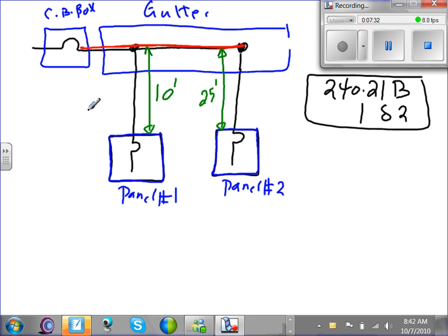All right. If you look at that, this is just a quick review of the 10-foot taps. Here's what the 10-foot tap tells you. Rule number 1, you can't go further than 10 feet. Duh, Chad, it's called 10-foot tap, so it goes without discussion, right? Rule number 2, the tapped conductor must be terminated at an overcurrent protection device that does not exceed the ampacity of the conductor.